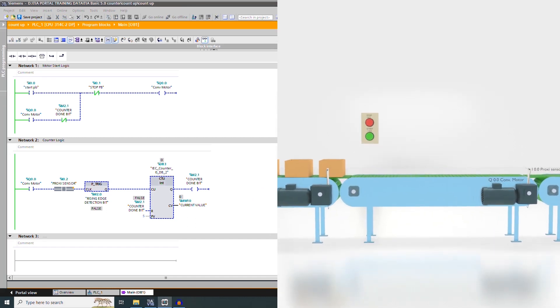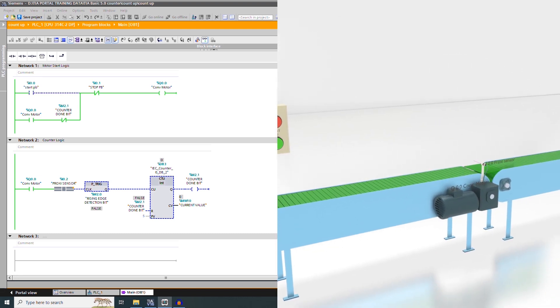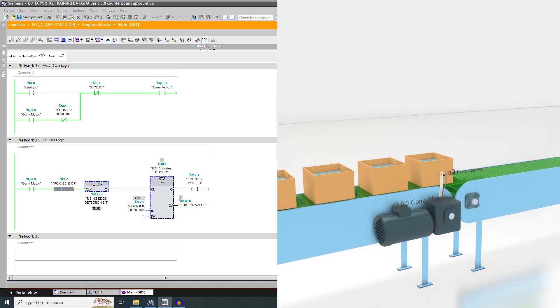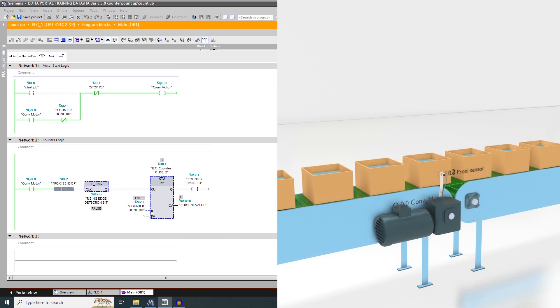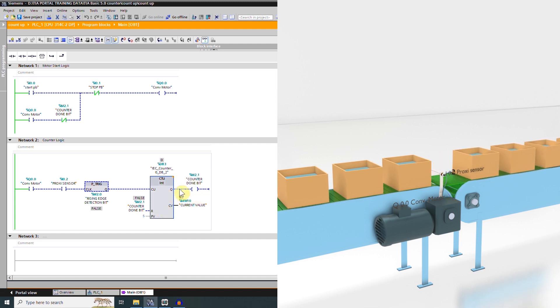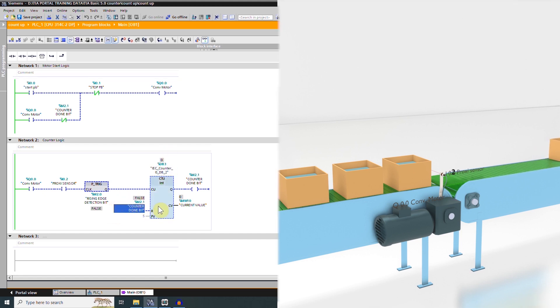As soon as we press the start push button I0.0, our conveyor starts to run and boxes start to move on the conveyor. Each time a box passes in front of sensor I0.2, the counter current value is incremented by one. As soon as five boxes pass the sensor, the counter current value reaches five, bit M2.1 turns on, and it latches off the conveyor Q0.0, stopping the boxes. At the same time, M2.1 resets the counter current value back to zero, making it ready to count five boxes again.